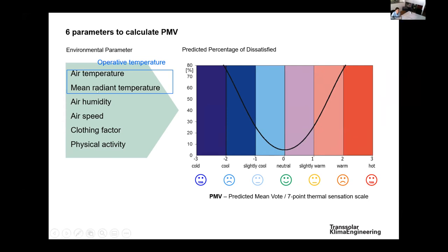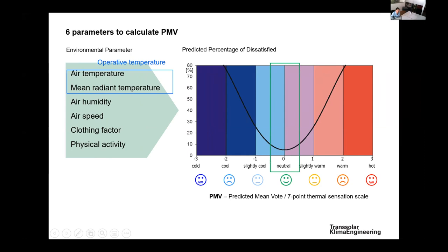The six parameters influencing thermal comfort are: air temperature, mean radiant temperature, air humidity, air speed, clothing factor, and physical activity. What we want to achieve in all indoor and outdoor comfort design is a predicted mean vote between plus and minus 0.5. Within this range, we are always at around 10% dissatisfied people, giving an overview of how these metrics relate to the statistical comfort of people on a global scale.